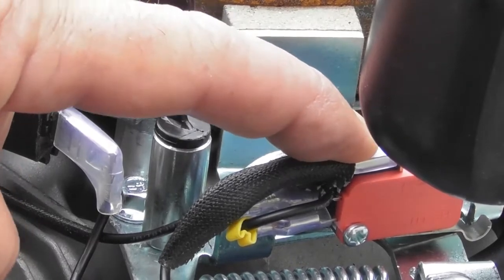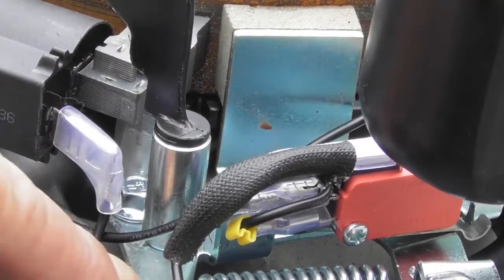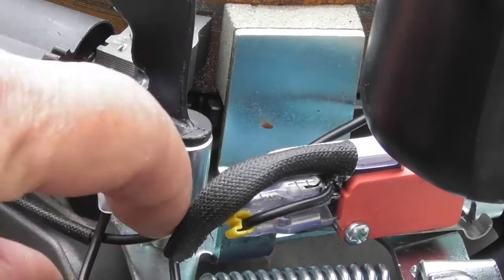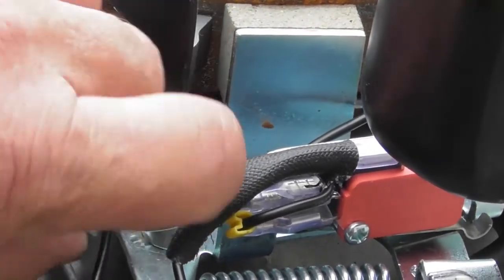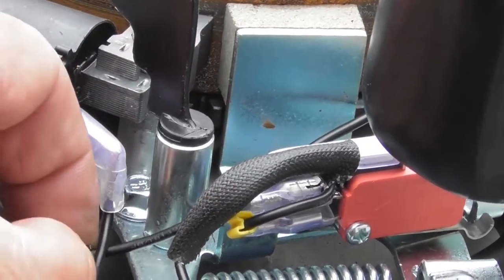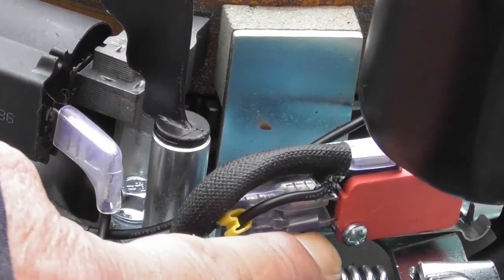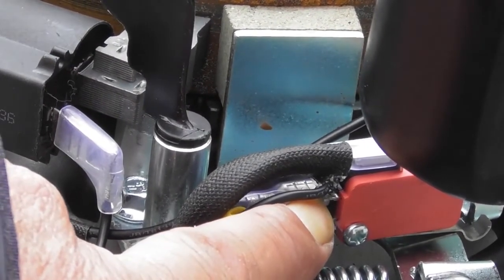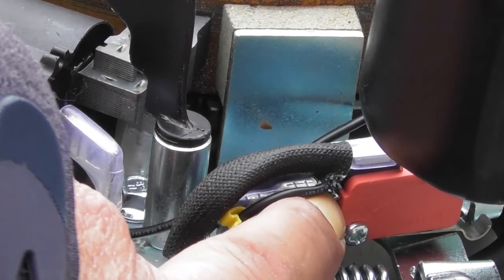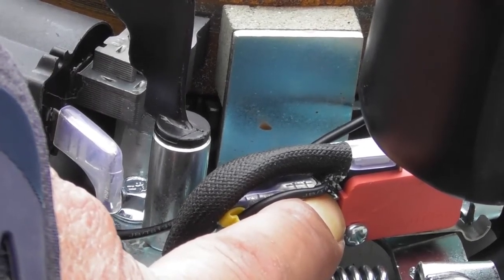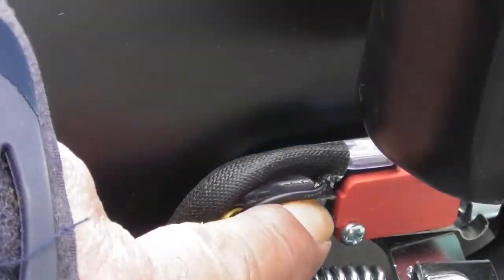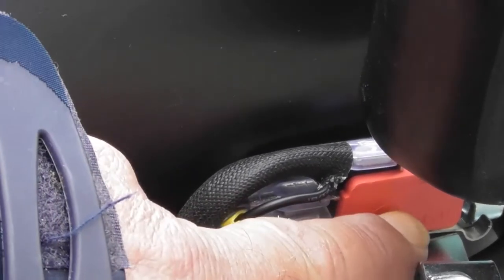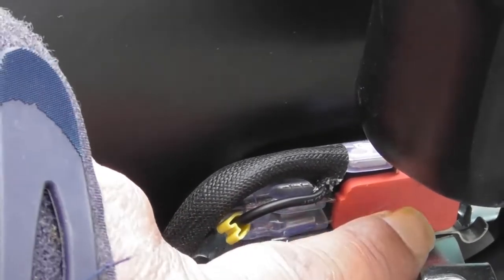So we need to check that we're getting negative coming out of that wire, the upper of these two. We need to check that when the OPC is pulled, we're getting negative out of there, which is the negative supply to the solenoid. Obviously if we aren't getting the negative out of here, it tells us that electrically it's this switch that is at fault.